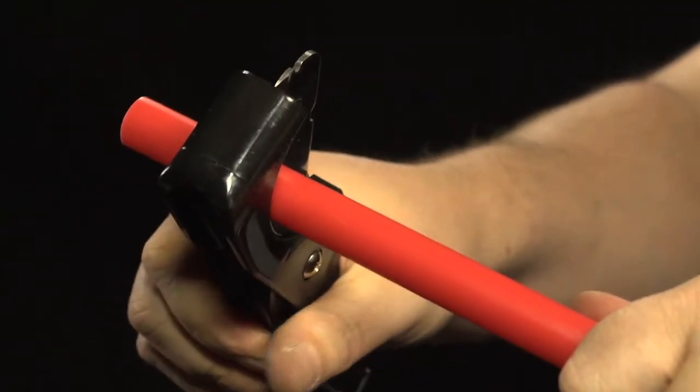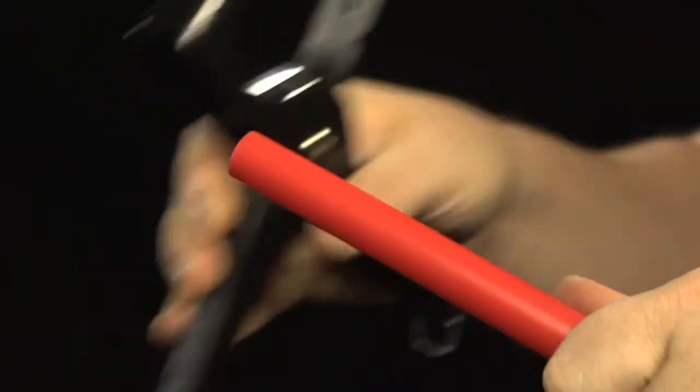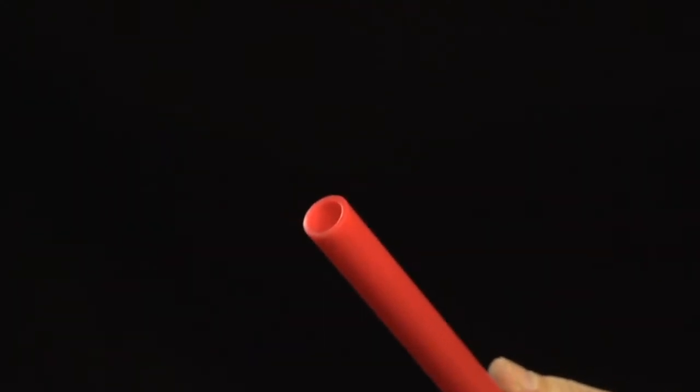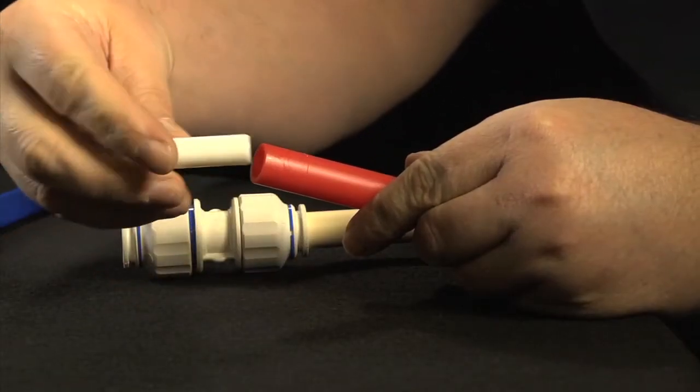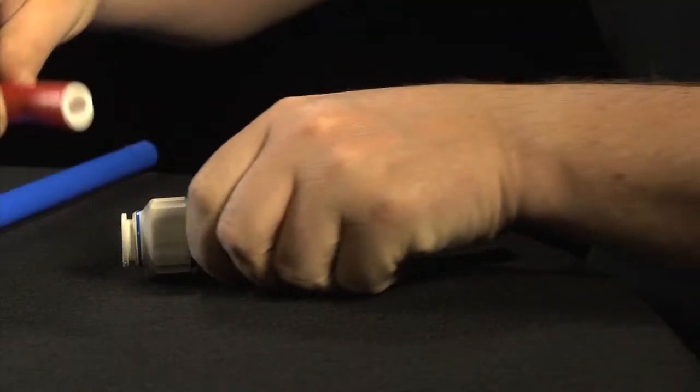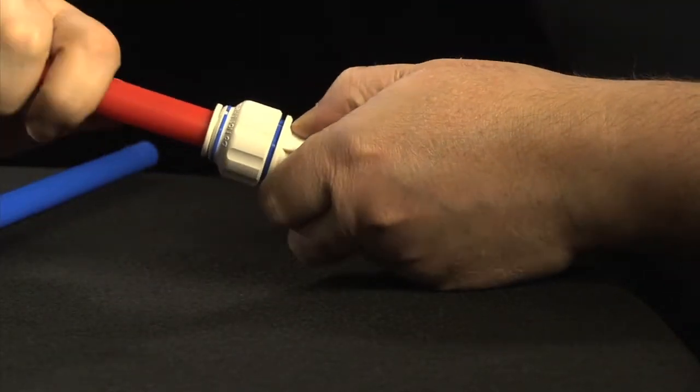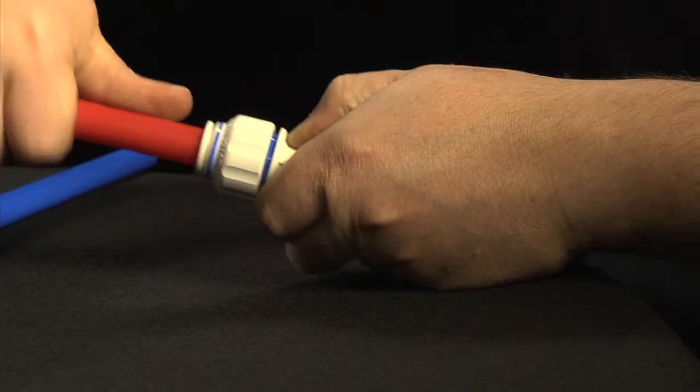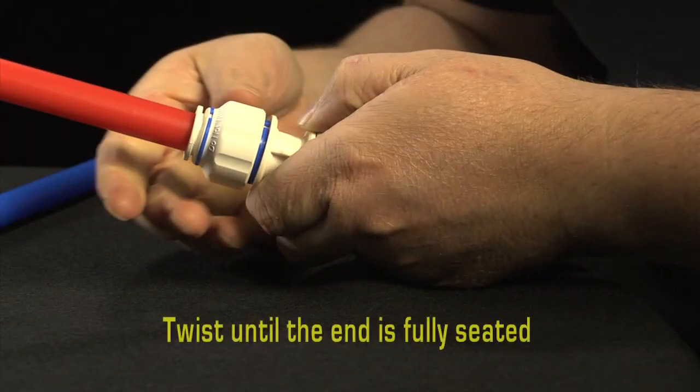To connect, squarely cut tubing or pipe to desired length, removing all burrs. Push fitting onto the end of the tube or pipe. Fitting will grip before it seals. Ensure that tubing or pipe is pushed into the fitting until the end is fully seated into the internal tube stop.